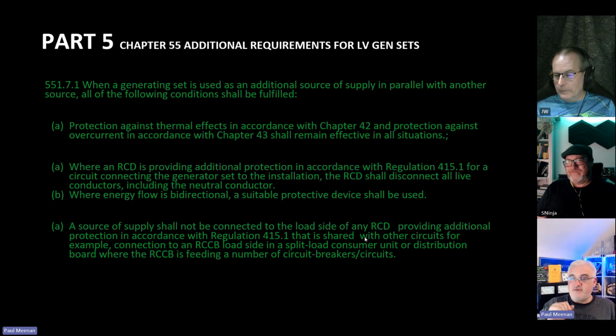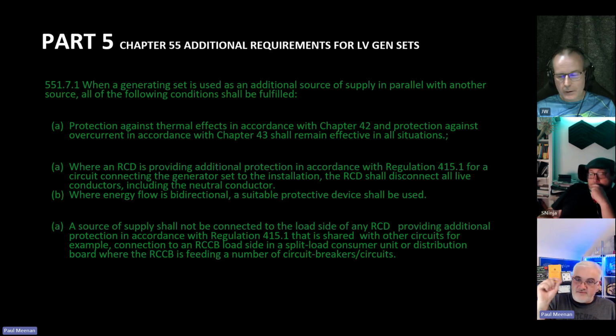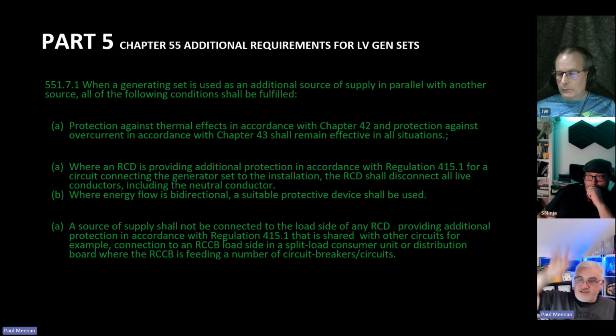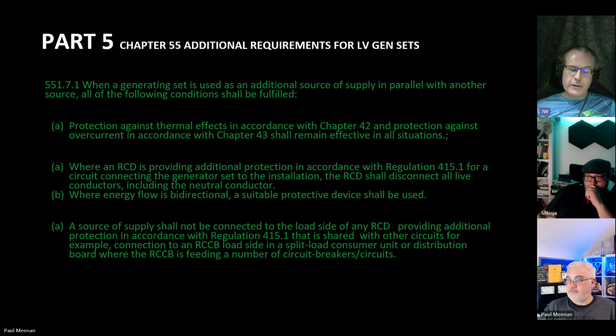And they're right, because what this means, guys, tell me if I'm wrong here, is that if you're connecting it into an MCB, let's say it's a connection from solar, it's going into that RCCB, but the fact of the matter is you're also feeding all them other circuits in parallel, which can be quite dangerous. So even though you may have your RCD disconnect, you're actually still parallel feeding a load of other circuits. So another example why split load boards should be thrown in the bloody bin. Yep, and they should have gone years ago when solar was first being put in.